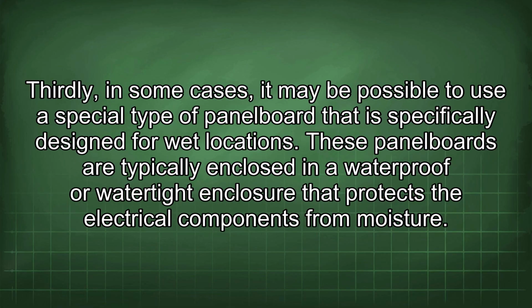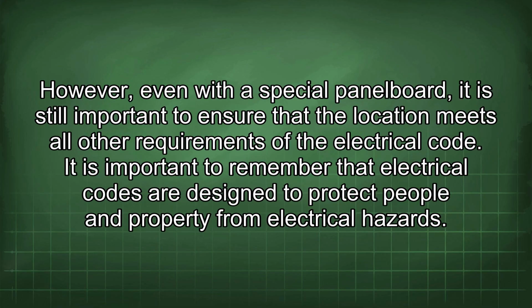Thirdly, in some cases, it may be possible to use a special type of panel board that is specifically designed for wet locations. These panel boards are typically enclosed in a waterproof or watertight enclosure that protects the electrical components from moisture. However, even with a special panel board, it is still important to ensure that the location meets all of the requirements of the electrical code. It is important to remember that electrical codes are designed to protect people and property from electrical hazard.